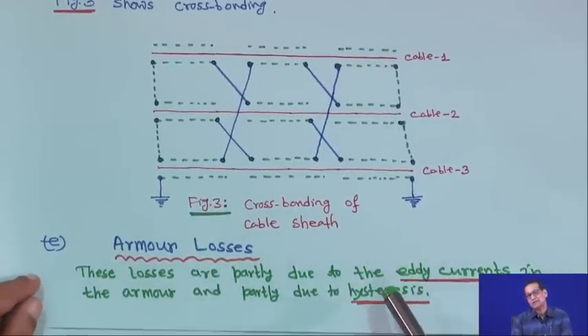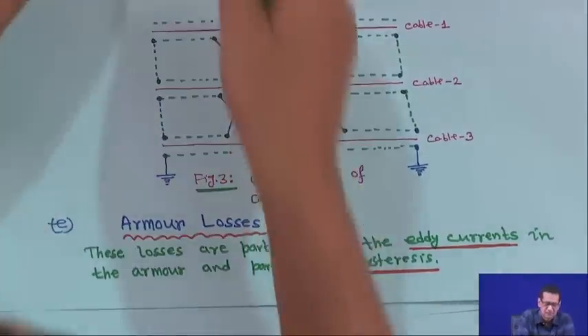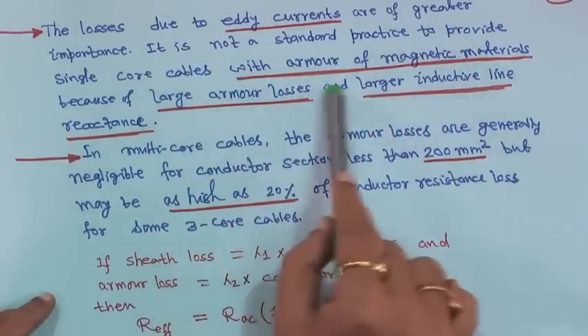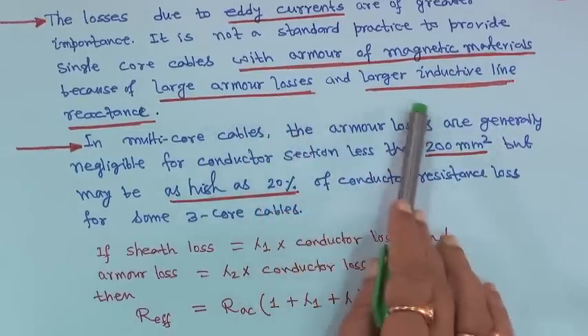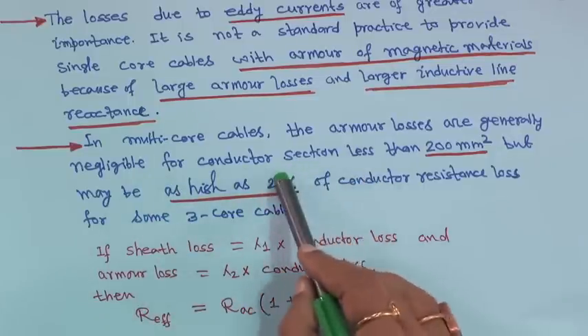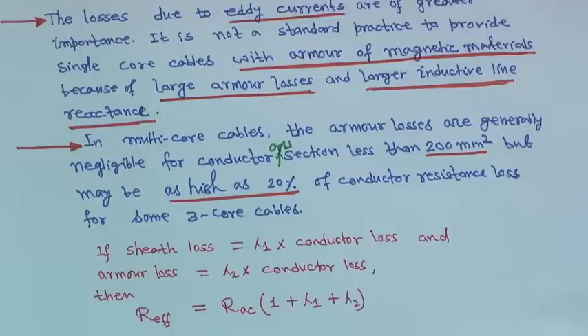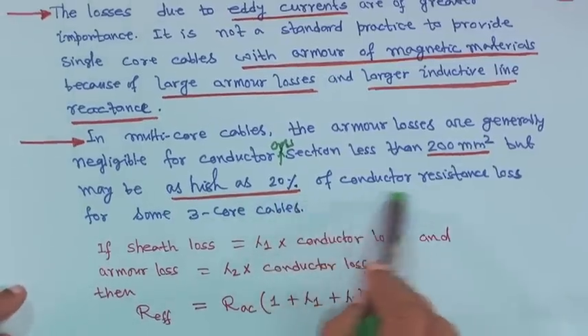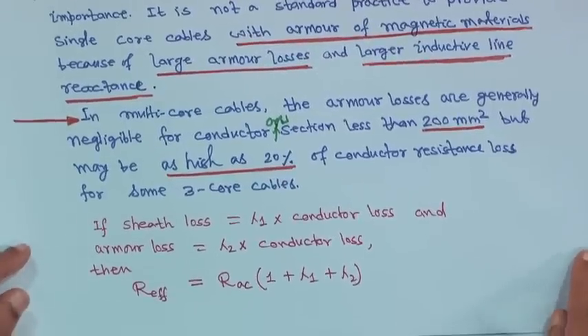Next, armour is there in the cable, so we have to consider armour losses also. Armour losses are partly due to eddy currents in the armour and partly due to hysteresis — both eddy current and hysteresis must be considered. The losses due to eddy currents are of greater importance. It is not standard practice to provide single core cables with armour of magnetic materials because of large armour losses and larger inductive line reactance. In multi-core cables, armour losses are generally negligible for conductor cross-section less than 200 mm², but may be as high as 20 percent of conductor resistance loss for some 3-core cables.